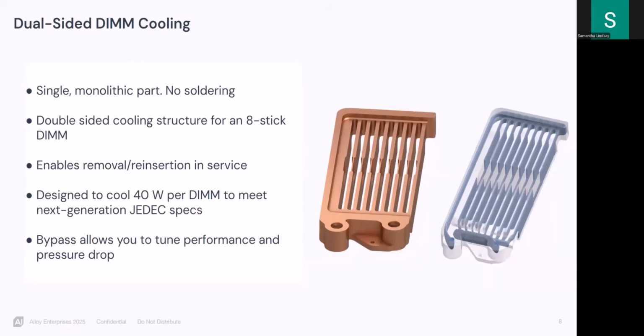Especially with memory, we want to be able to upgrade in the field and replace sticks that fail in the field. So this is designed for tool access, enabling removal and reinsertion in service. This particular design is already in simulation, and we're showing that we can cool 40 watts per DIMM to meet what we're projecting the next generation JEDEC specs to lay out for MR DIMM.